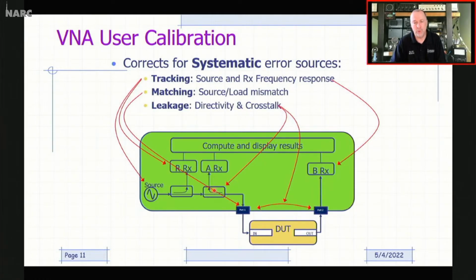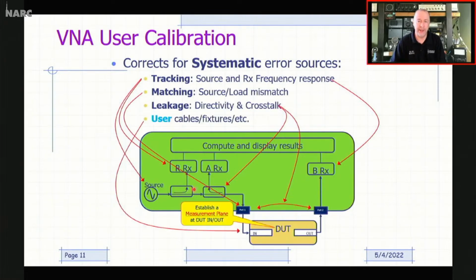And similarly, we could have directivity issues with our measurement couplers here. Directivity means it's a non-ideal thing about a coupler, where a directional coupler ideally will sample part of the signal going in one direction and not at all from the other direction. But the reality is they do respond from the opposite direction as well. And that's something called the directivity of these couplers. And part of the calibration can measure that, and again, mathematically remove that. And then, of course, we've got the user cables, fixtures, etc., that will help us to establish the measurement plane at the ports of our DUT.